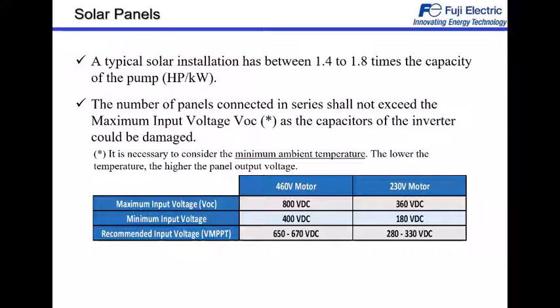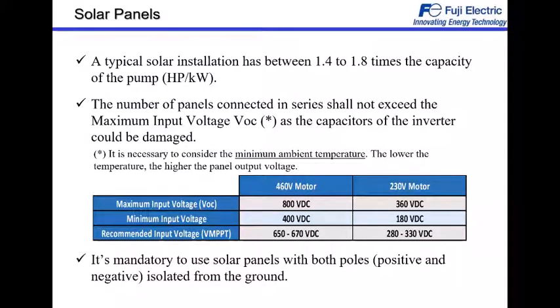Otherwise, we could damage it. Here we can see, depending on whether it's 230 or 460, the minimum and the maximum voltage that we can fit, and some recommended voltage. But again, it is necessary to consider this at the minimum ambient temperature, because the lower the temperature, the higher the panel output voltage is. It looks opposite. On a very sunny day, and if it's a colder day, sure, with the same irradiation, we will have higher output voltage. And important, it's mandatory to use solar panels with both poles, positive and negative, isolated from the ground.